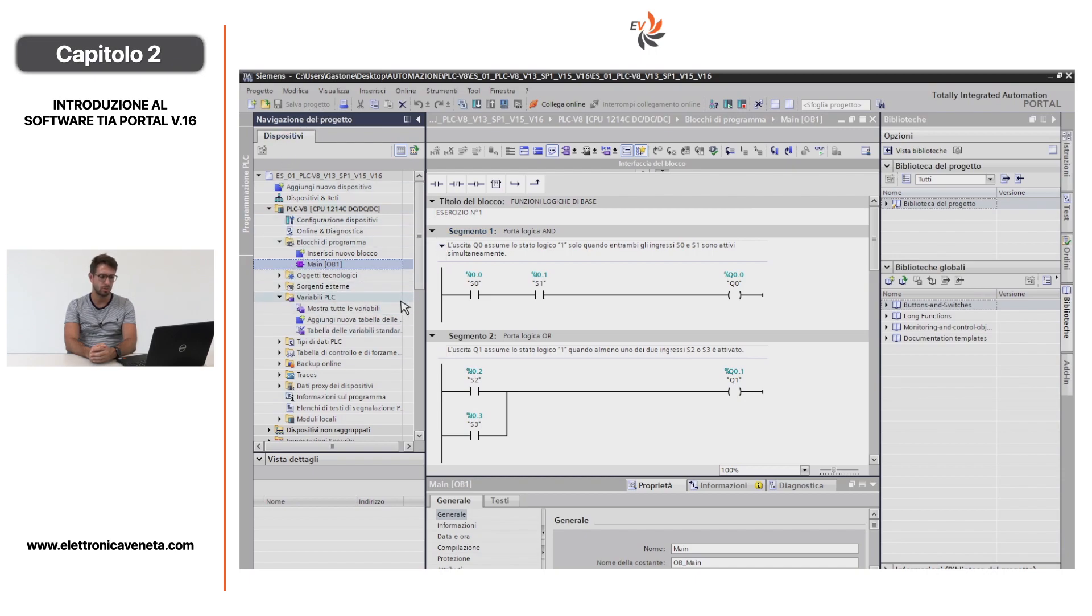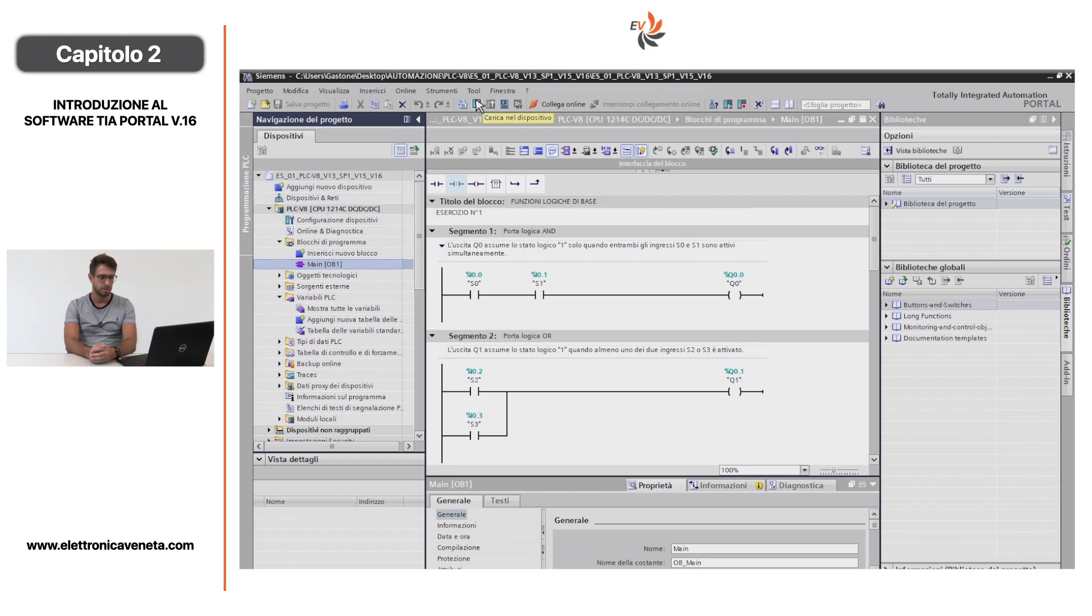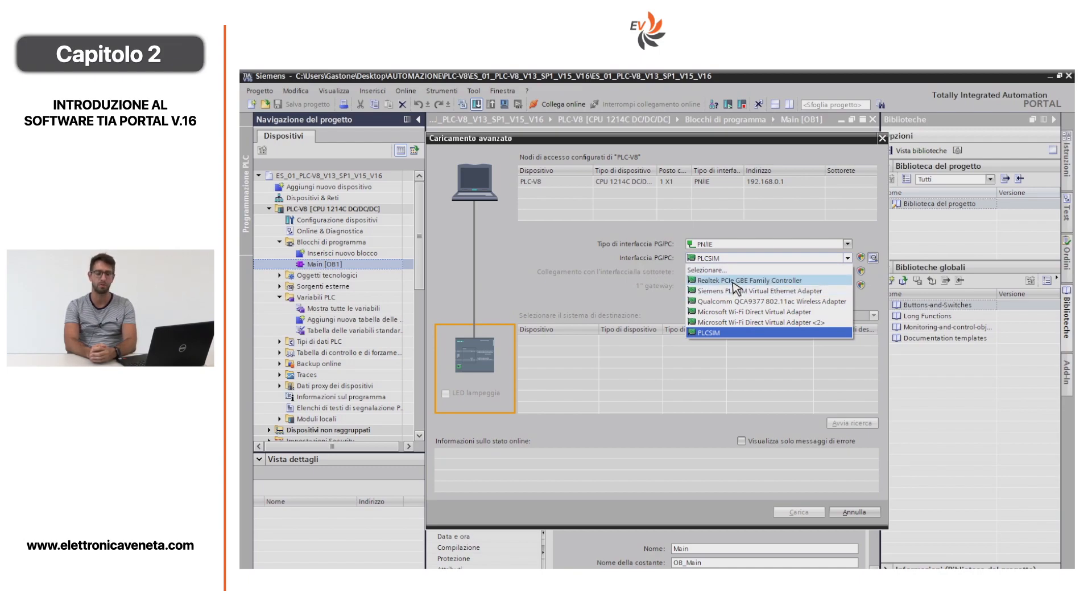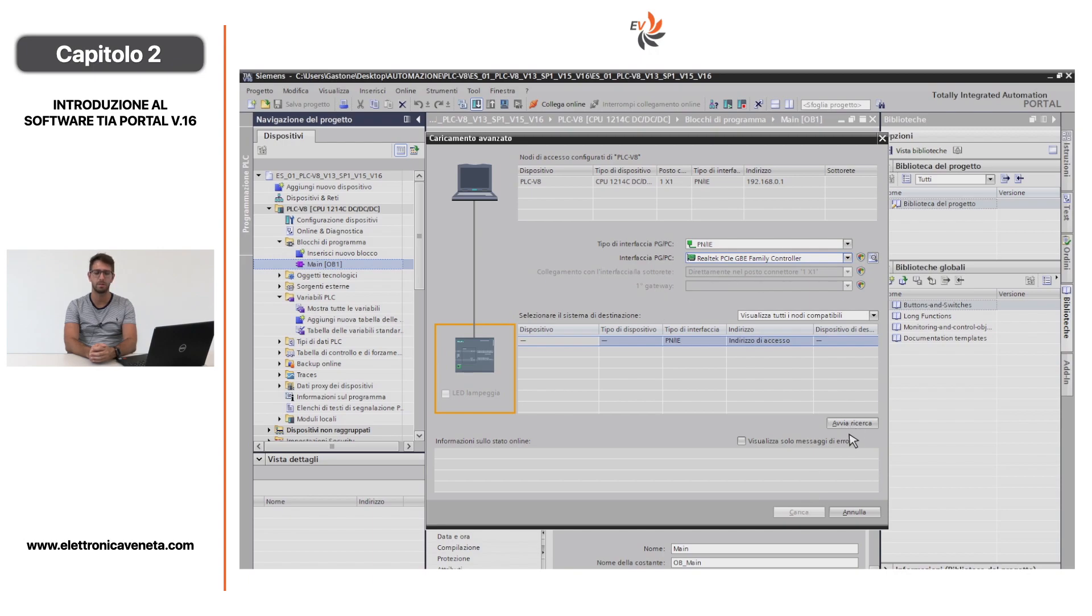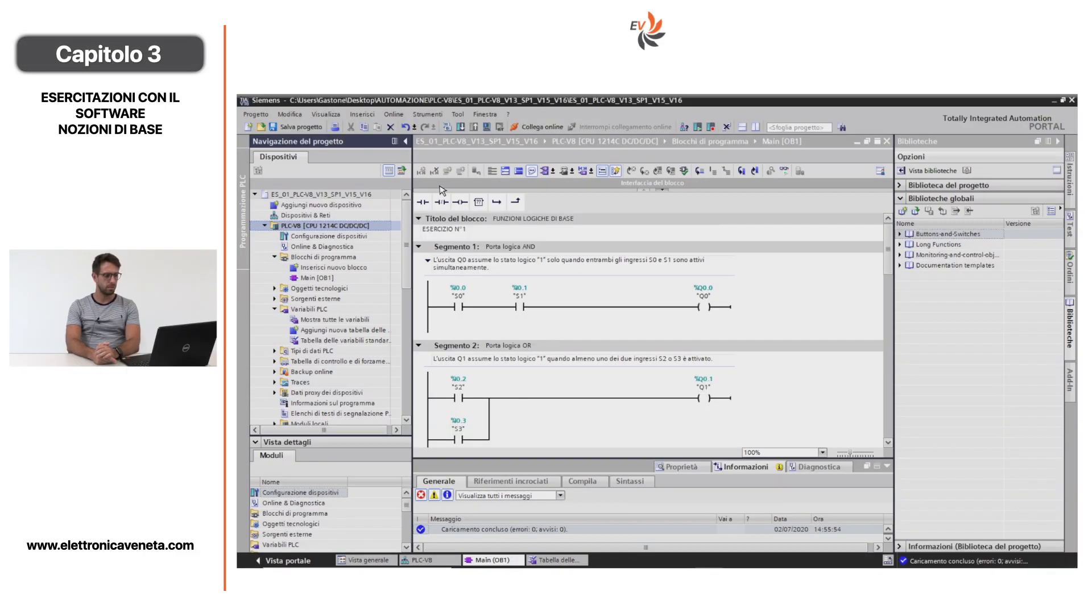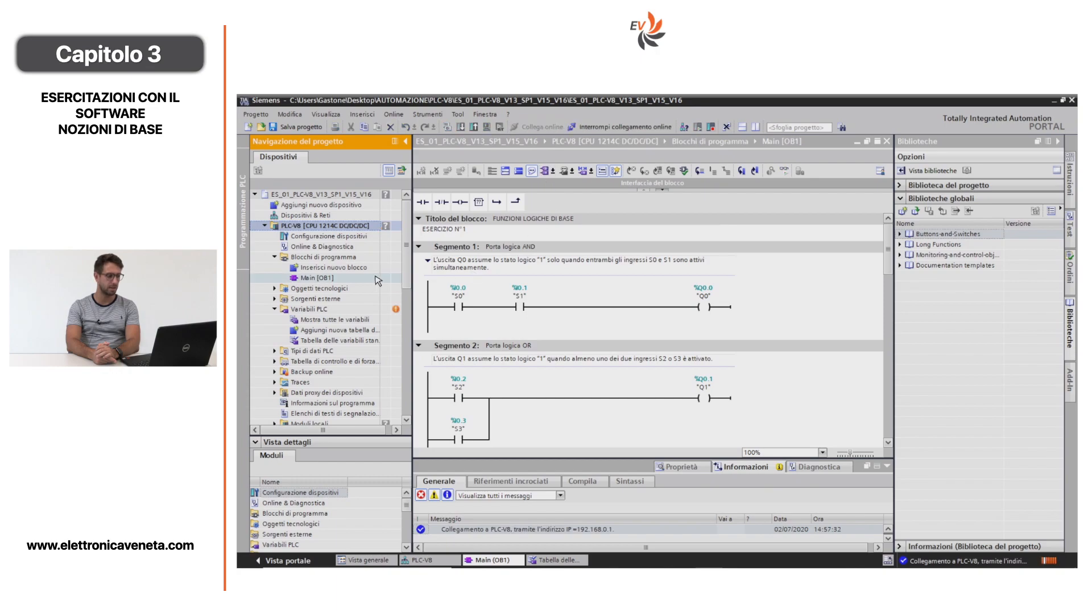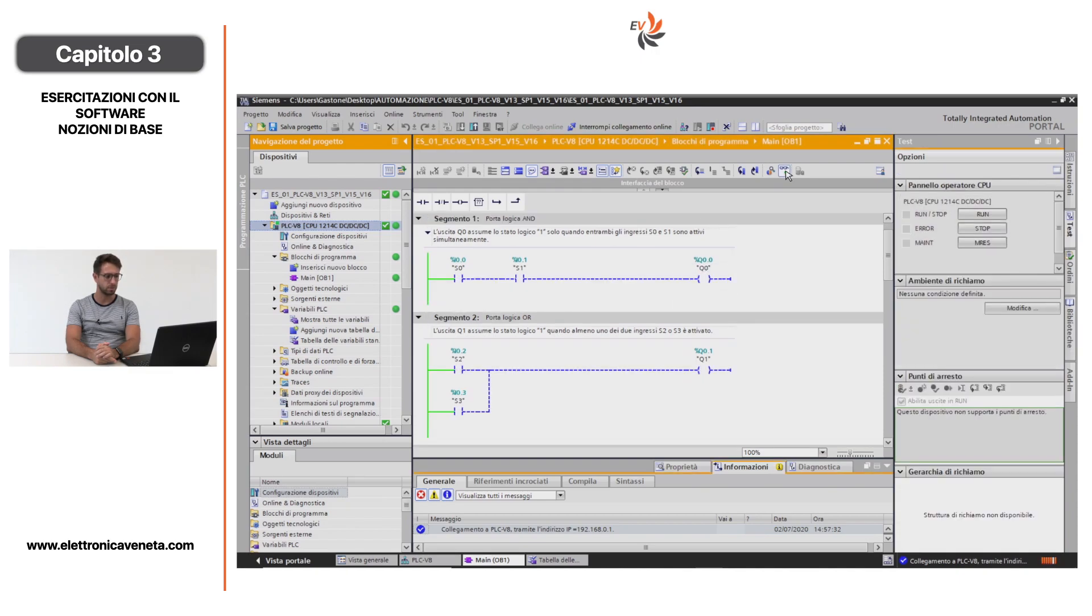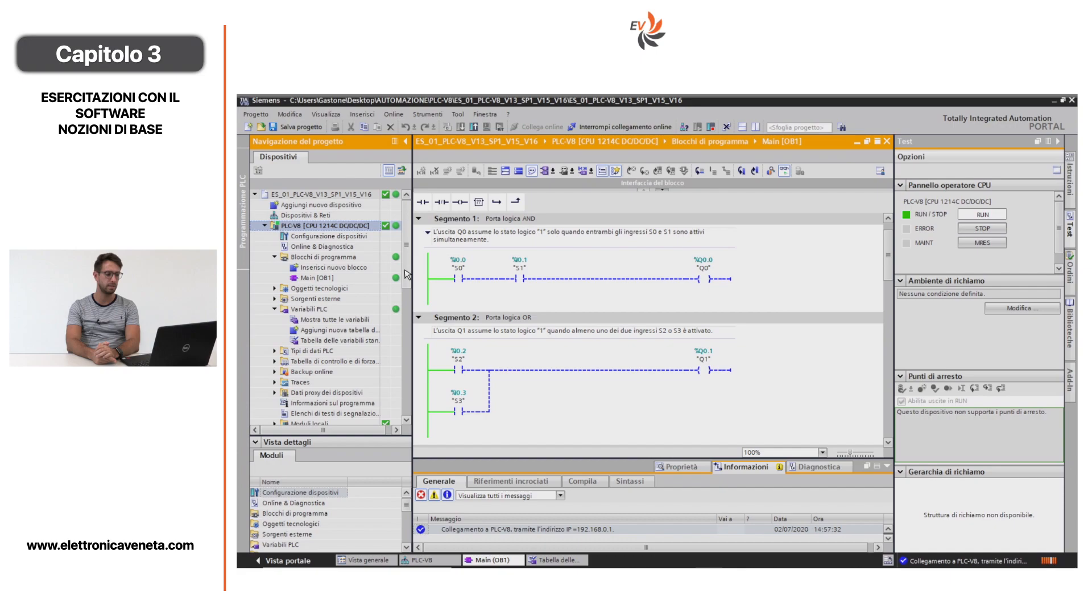Abbiamo concluso la descrizione del programma. Una volta concluso si può compilare o direttamente caricare il programma nella mia macchina. Clicco sempre in PLC V8, schiaccio caricamento nel dispositivo, mi si aprirà una nuova finestra con la quale si seleziona l'interfaccia di comunicazione, in questo caso PROFINET, e si avvia il caricamento del software nella macchina. Una volta caricato il programma, si passa al collegamento online. Per verificare il giusto collegamento si nota nell'area di sinistra i pallini di ogni programma che sono correttamente collegati. Ora passiamo a CTRL ON-OFF cliccando sull'icona a destra. Adesso possiamo andare a variare gli stati dei miei ingressi. Adotteremo il simulatore a bordo del mio trainer.